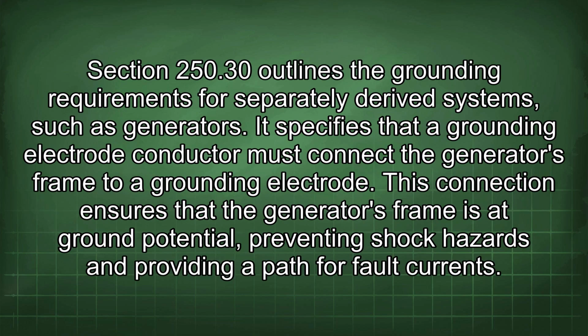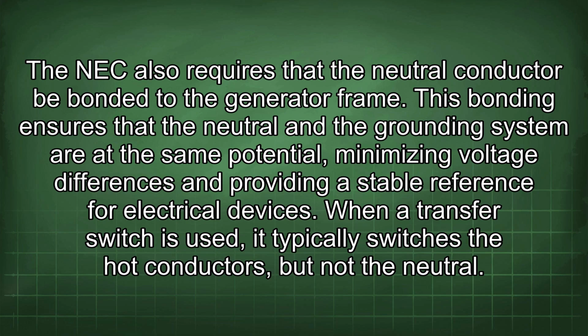Section 250.30 outlines the grounding requirements for separately derived systems such as generators. It specifies that a grounding electrode conductor must connect the generator's frame to a grounding electrode. This connection ensures that the generator's frame is at ground potential, preventing shock hazards and providing a path for fault currents. The NEC also requires that the neutral conductor be bonded to the generator frame. This bonding ensures that the neutral and the grounding system are at the same potential, minimizing voltage differences and providing a stable reference for electrical devices.